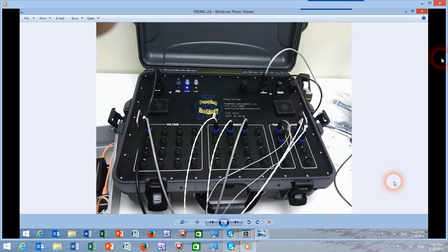Well, let's go through the system description and the basics of how it operates. Well, you see the box that is monitoring a multi-channel system, including power, the pressures, temperatures, vibrations, and the stream. When the system is energized and attached, with the wires coming from the probes attached to the system, it then transmits the signal to the cell tower, from where it is connected to the website, and you can get information about your pump live, online, any place in the world, any time of the day, 24/7. You, as a manager or engineer or maintenance manager, operator, have access to the system directly, either through your SCADA system or directly online, as we'll just show in the following couple of slides.